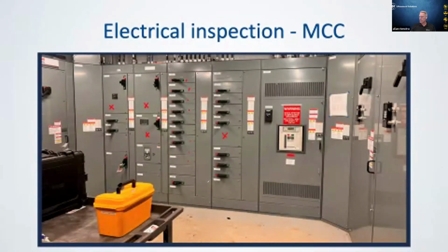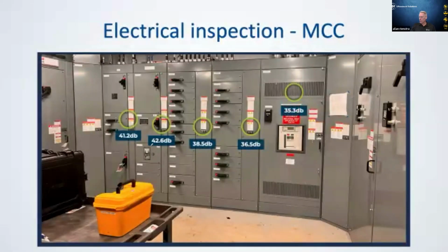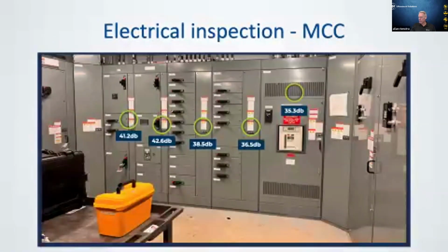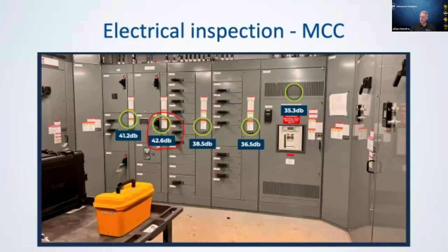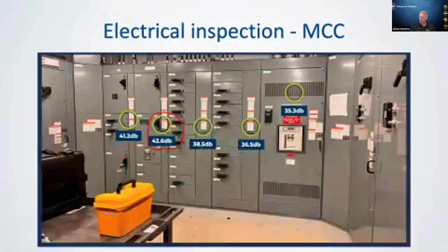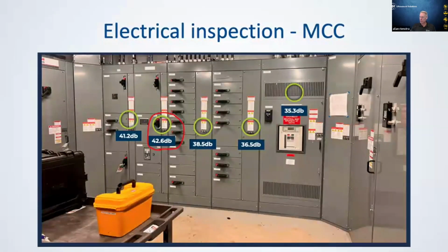And so in this particular case, the high point, or the most noise, was coming from this part of the MCC cabinet. So what this did is it enabled us to put our focus into here. We didn't need to open them all up. We just needed to open up this one because that was the loudest point. Once that was opened and the defect was eliminated, we closed it all back up again. All of these values went back down to a more normal, uniform level.